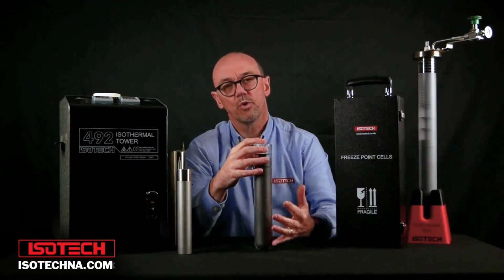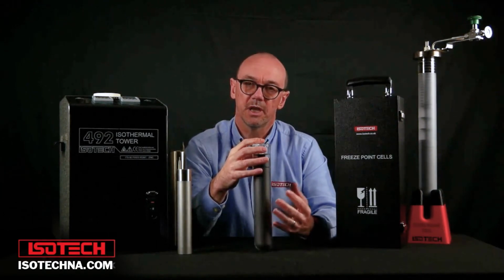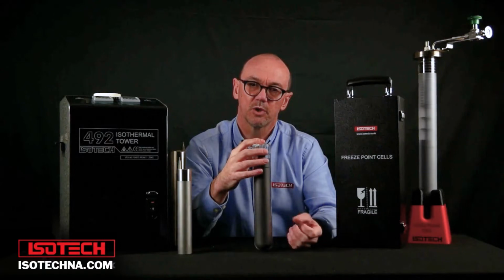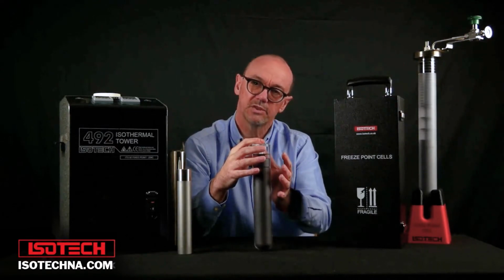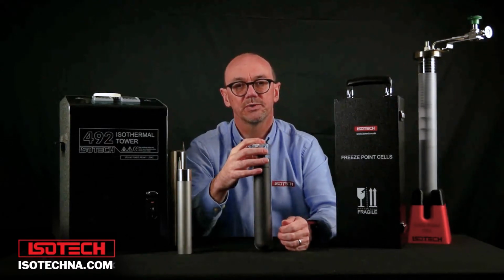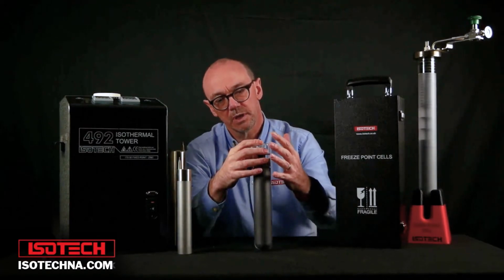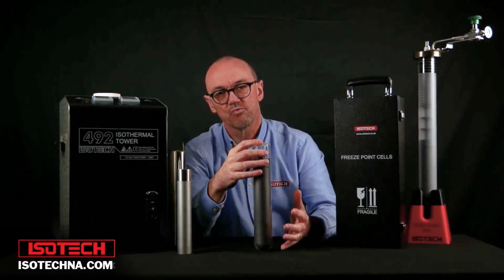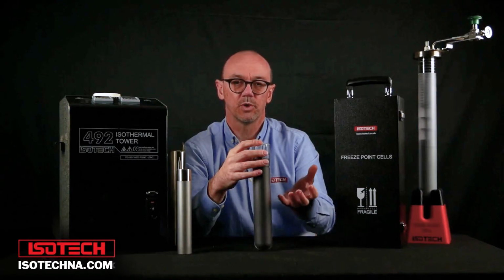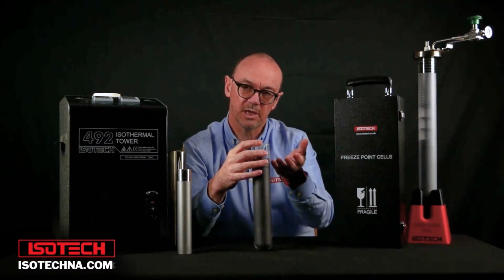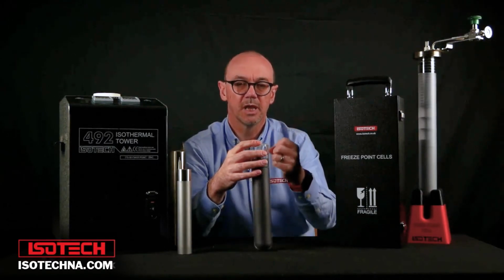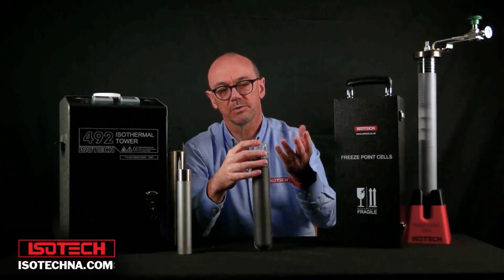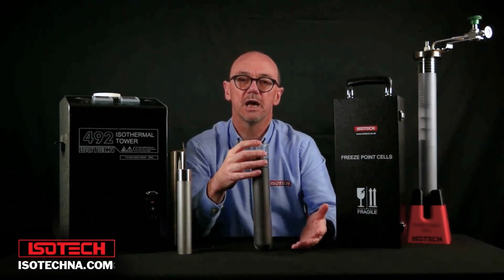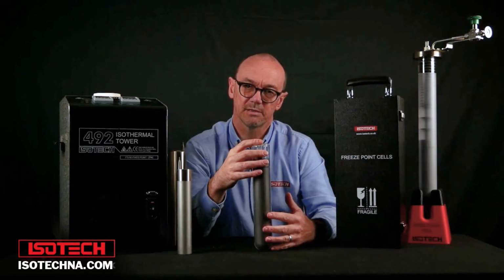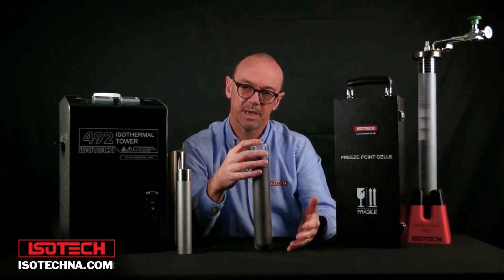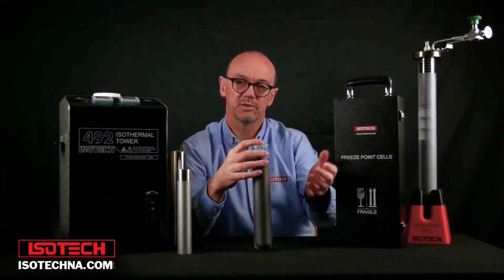So before I was to use the cell at a high temperature, I'd wear some powder-free latex gloves. I would wash and clean the cell with acetone to remove any grease. And these cells don't go directly into the furnace, they go into, we call it a basket, with some insulators and some metal reflectors. Again, I'd clean all the metal parts. I'd fire those at a higher temperature than I'd use the cell at. And then I'd put the cell into the basket, clean, and then put it into the furnace.